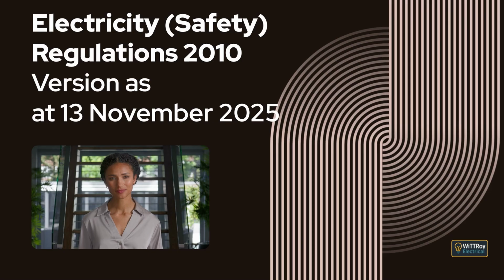Reg 61, a rule about 3-pin flat-pin socket outlets in low-voltage installations. This regulation explains that if a 3-pin flat-pin socket outlet with dimensions specified in AS/NZS 3112 is installed in a low-voltage installation, it must only be supplied at standard low voltage. It also explains that the earth continuity conductor must be connected to the radial slot, and that when the socket outlet is viewed from the front, the order of connection in a clockwise direction is the earth continuity conductor, then the active conductor, and then the neutral or other conductor. It finishes by explaining that installing such a socket outlet in any other way is an offence and carries a Level 2 penalty. This part covers rules for high-voltage installations.